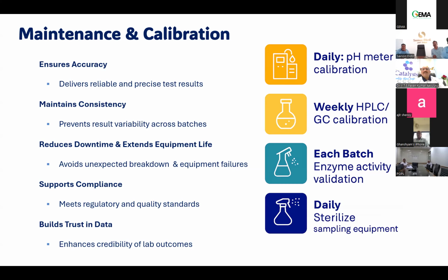When it comes to maintenance activities, for each equipment there should be a clearly defined cycle. Like the pH meter, it has to be calibrated on a daily basis. HPLC and GC equipment have to be calibrated on a weekly basis. Enzymes which we use should be validated for each batch. Whenever we get a new enzyme batch, we should be able to validate it. And the sterilization of the sampling equipment and the analysis place, lab benches, everything, has to be done on a daily basis. If we do this properly, we will be 100% confident that our results are trustworthy and accurate, and we will be able to take decisions based on the data in a proper way.